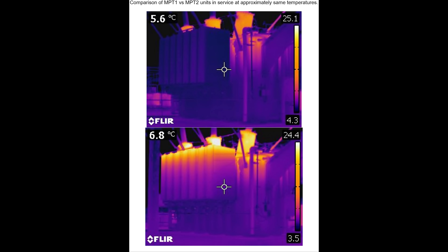So we had to de-energize it and lock it out. Apparently there are bleeder valves on the top of each radiator, and he was able to bleed the air out of each individual one. It was as simple as that — air trapped at the top. That air pocket was preventing oil from returning to the top of the transformer, where it would flow back down and begin the cooling cycle of rising as it heats and falling as it cools. Sure enough, there was a bit of air in each radiator.